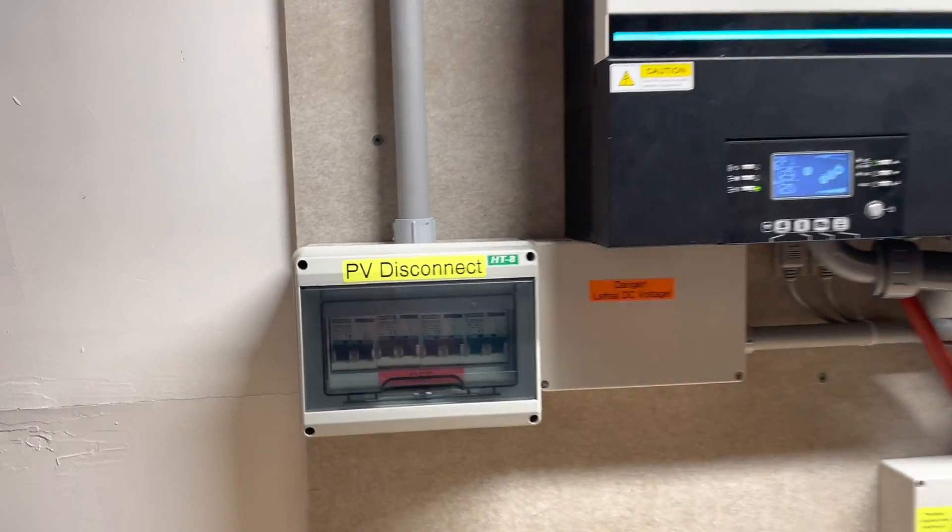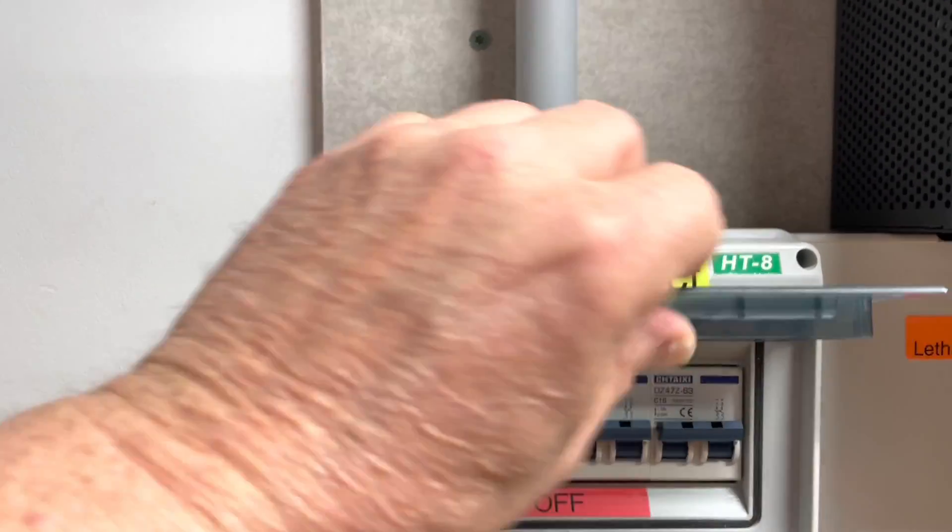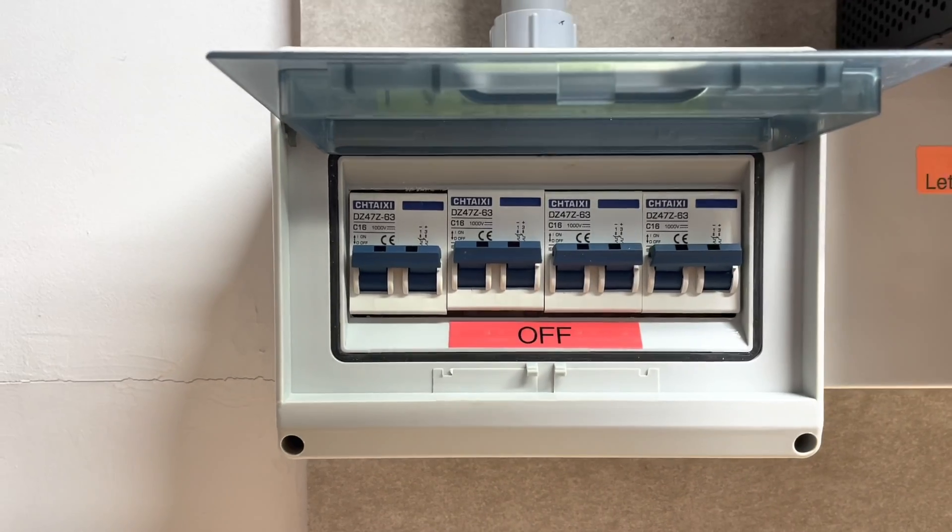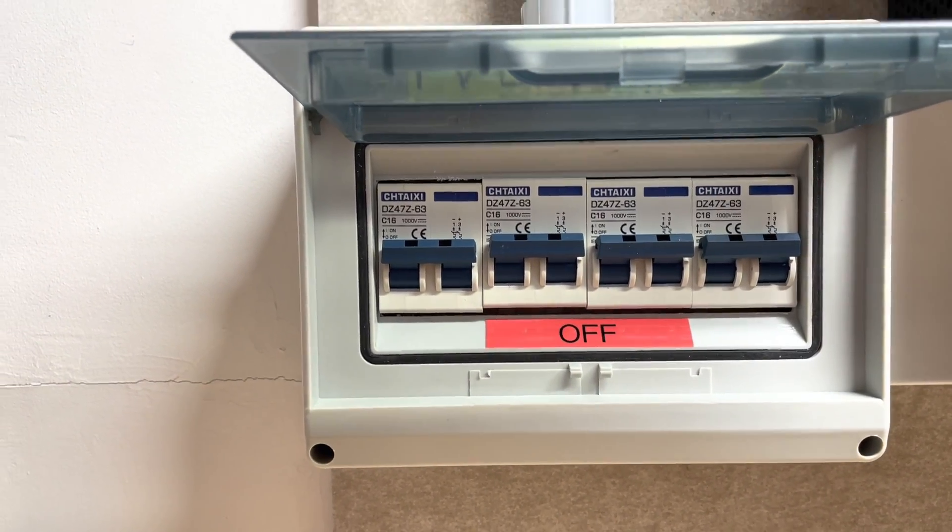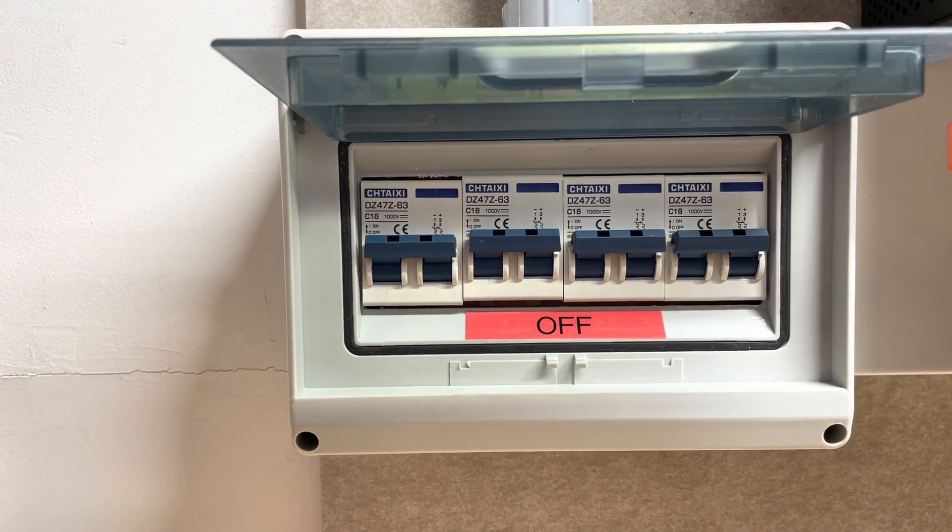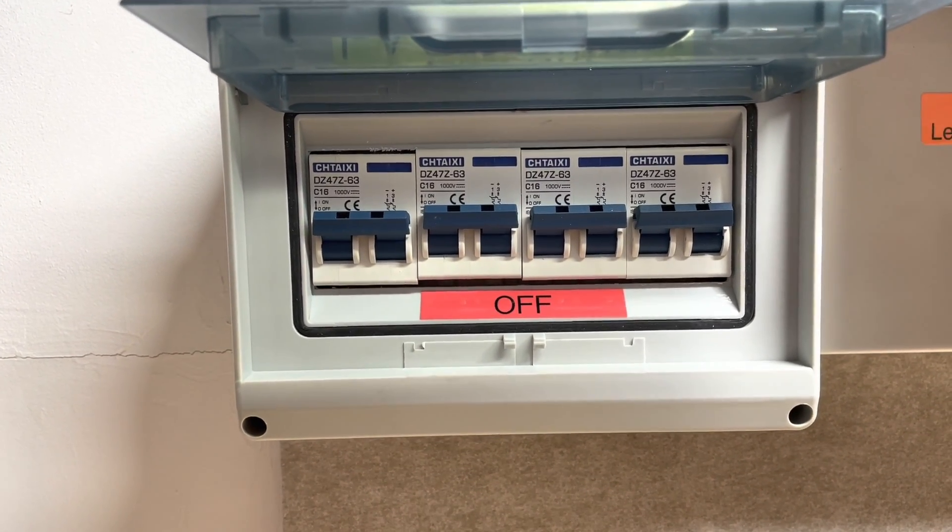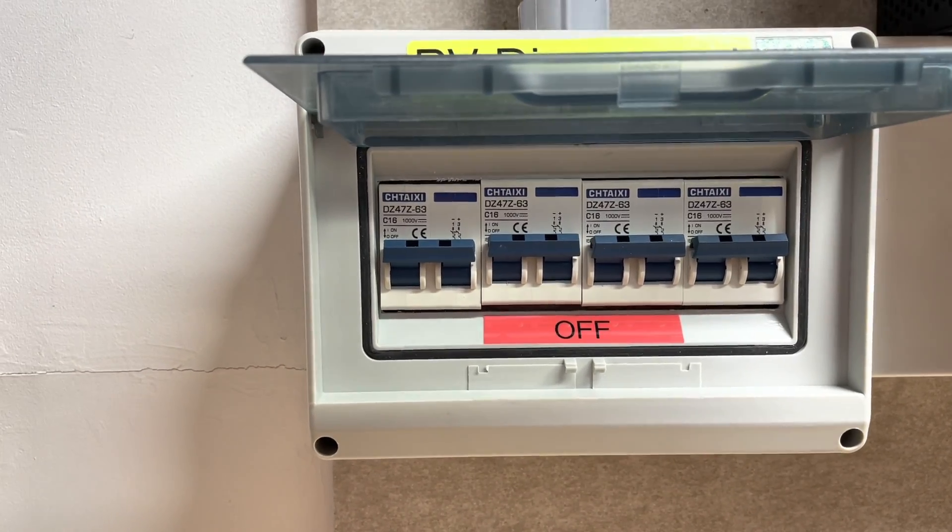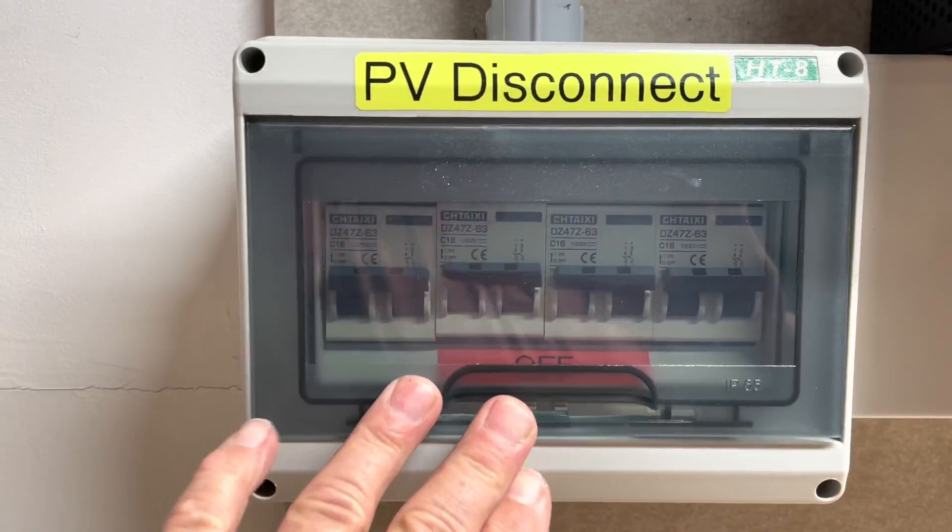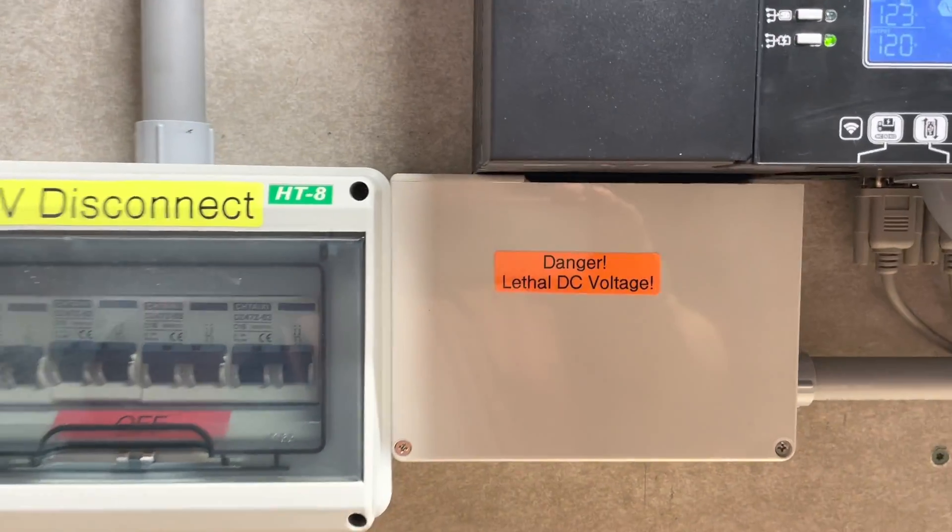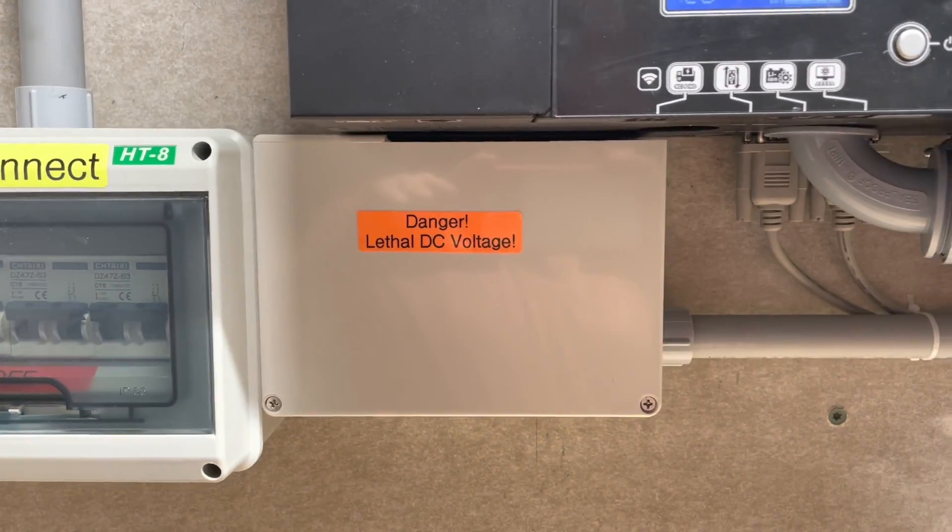We start here with the solar. Got these thousand volt rated DC breakers, and you want to make sure you put special attention to the polarities when you're working with DC breakers or you can have a problem with fire on your breakers. I've got the cover for the MC4 connectors in there and we have more connectors going into this unit here.